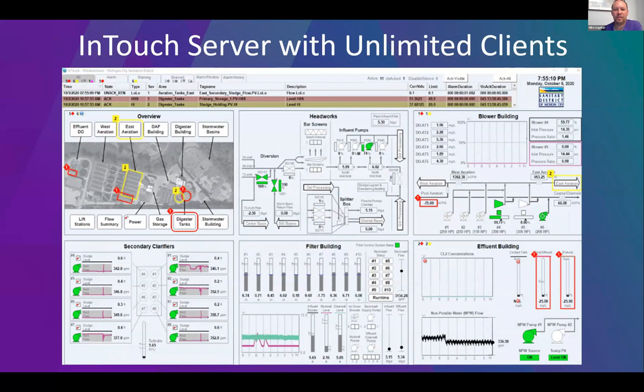Here you can see an example of an InTouch application leveraging the Situational Awareness library. A lot of the elements are grayscale, but color is used sparingly to draw the operator's attention to things like abnormal situations, alarms, or items that are on or running — limiting color where things are running normal. There are trend pens on the bottom left-hand side for an overview of what's going on in your environment, both in real time and in a historical trend, alerting the operator's attention to what matters most.